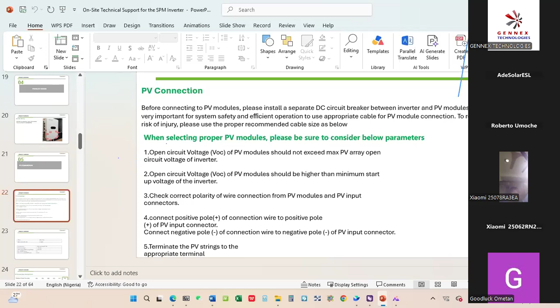Then terminate the strings appropriately. Terminate the strings where they are to be. For example, let me say you have two strings of PV coming from your roof, and for one string, you connect the positive of one of the strings to one MPPT tracker. Instead of connecting the negative side of that same string to the MPPT, you went and connected the negative side of the second string to the inverter. You are going to damage the input pole of that inverter. So always make sure you terminate your PV string appropriately.